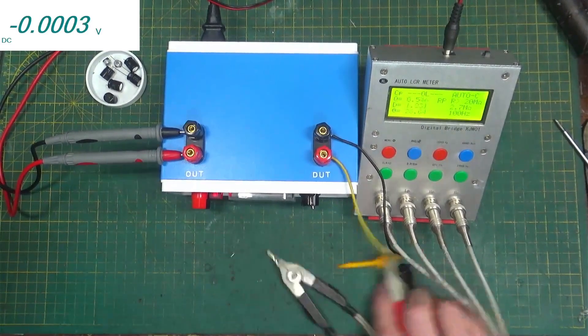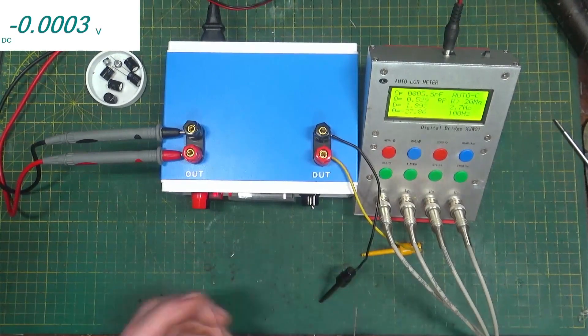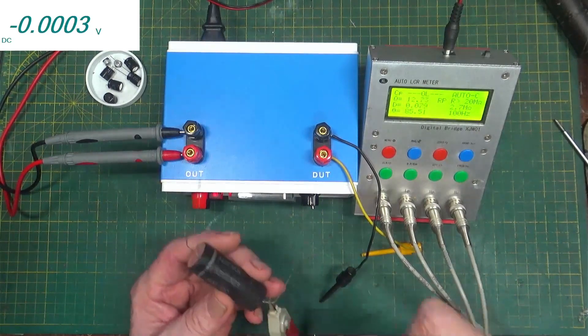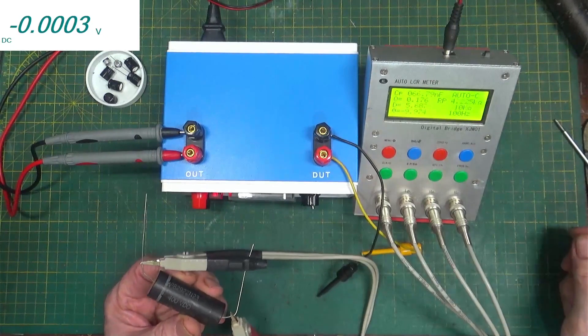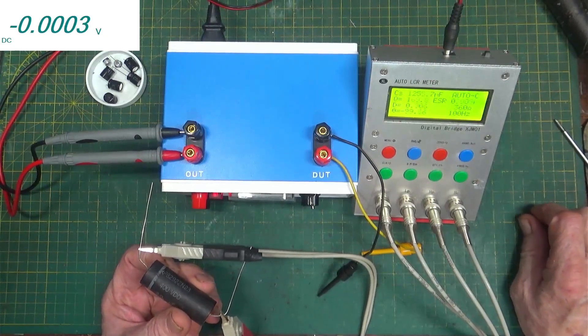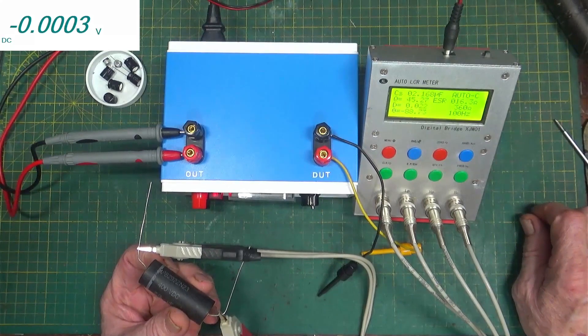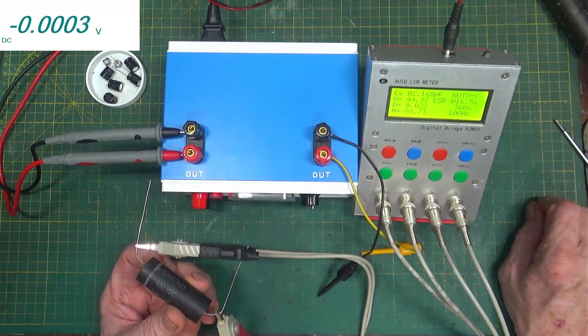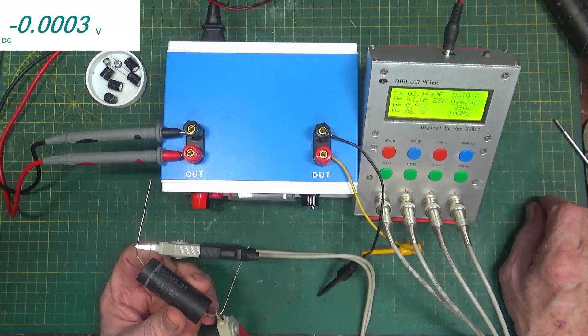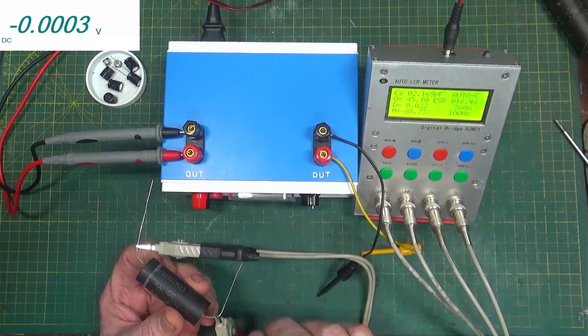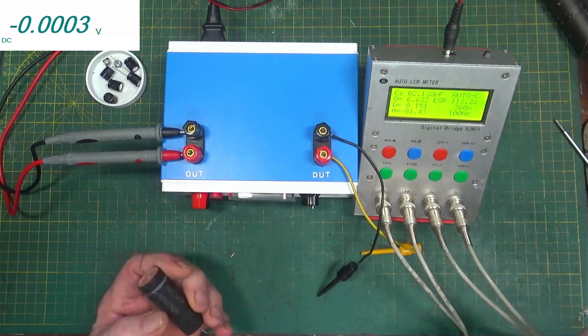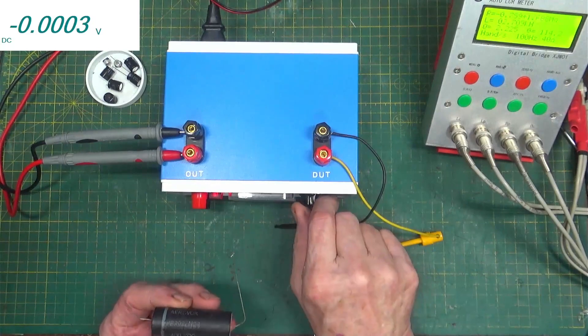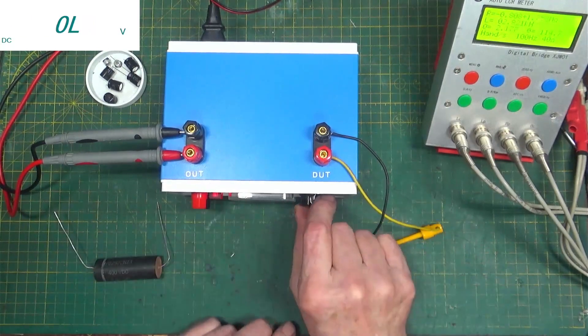Here's another one. Let's try this. Let's measure this just to make sure. This one is a two microfarad, it is not an electrolytic. We're going to measure this and see what it says. Give it time to settle down. 2.1 microfarads. It says 16 ohms at 100 hertz, minus 88 degrees. So that shows us a pretty fair cap on this system here.